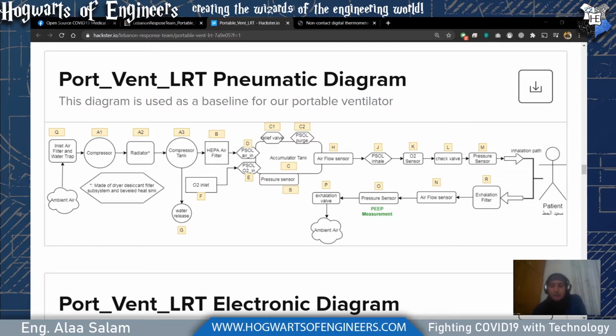Pressure sensor M measures the pressure on the inhalation end. And this pressure is what we use in order to calculate if the tidal volume, so the volume of air going from the accumulator tank to the patient, is the right amount that we set. Now, I'm not going to go too much into the ventilator, but there are specific parameters that need to be monitored to make sure that the amount that we set as a user is being given to the patient properly.